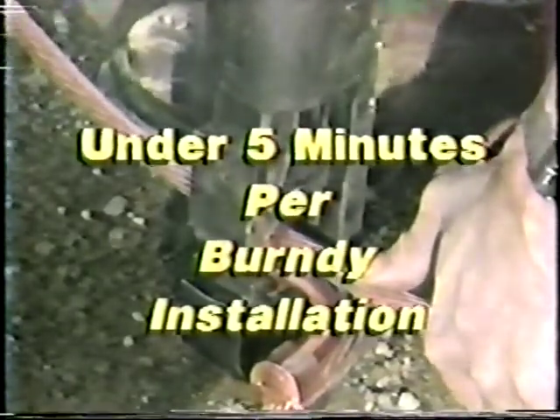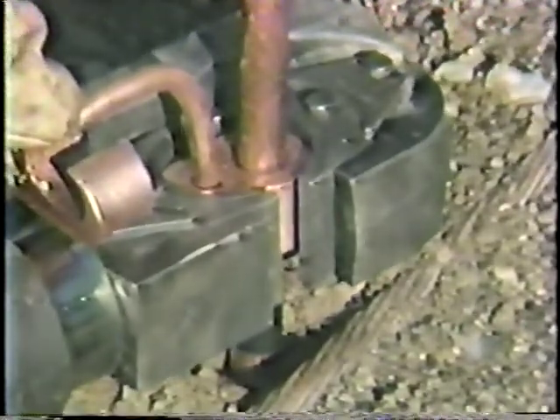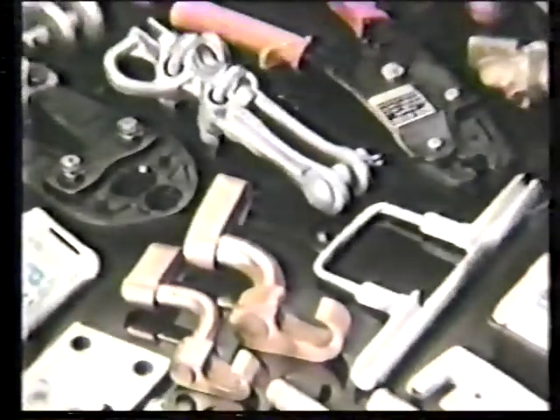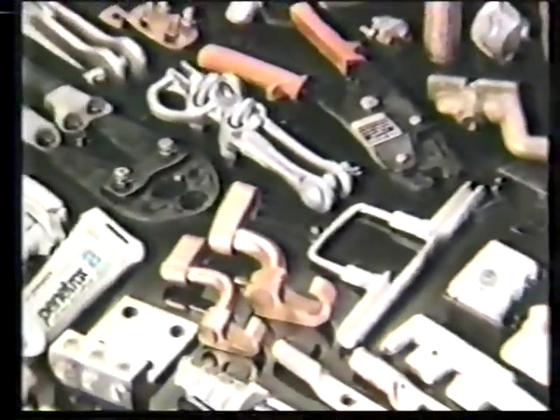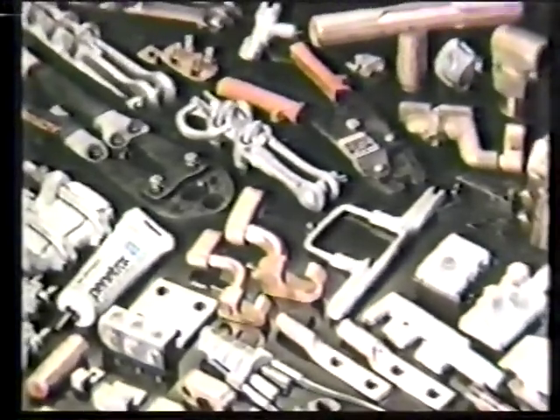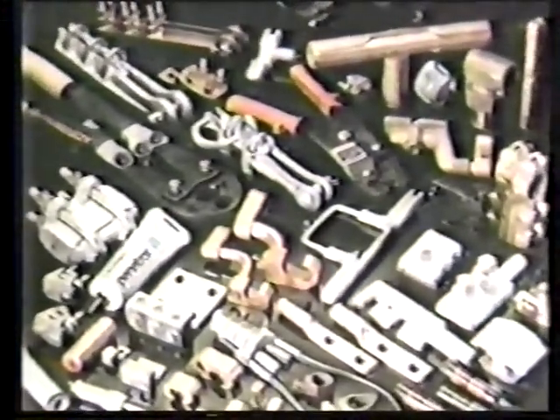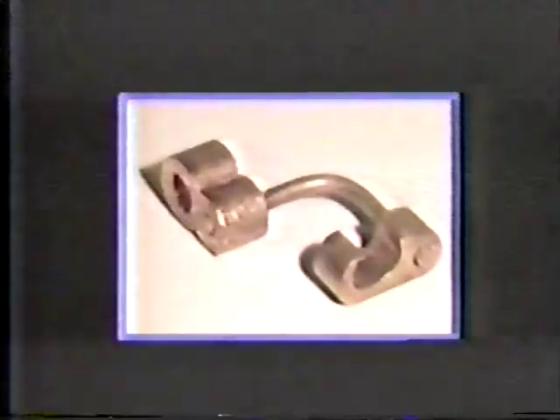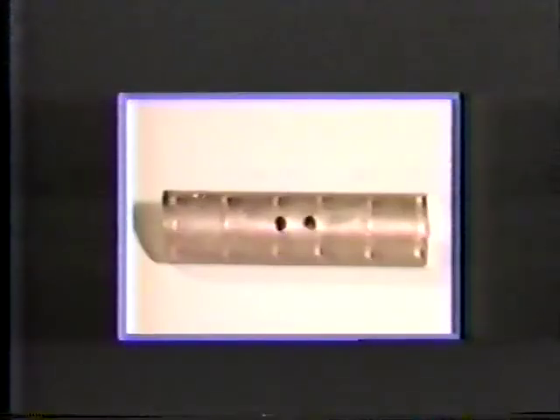A typical Burndy connection requires under 5 minutes. Therefore, it costs much less to install Burndy, even if you have the required exothermic molds. In addition, our compression system eliminates many of the safety hazards and wet weather job delays associated with exothermic installations. Burndy can provide all of the products necessary to complete your installation, including a full line of compression and mechanical connectors. Now let's examine Burndy's extensive line of compression products, specifically designed for ground system installations.